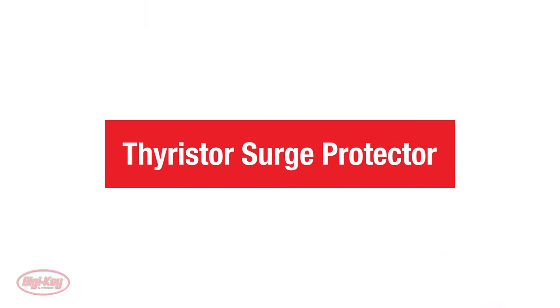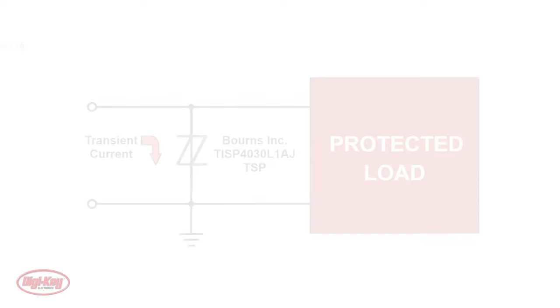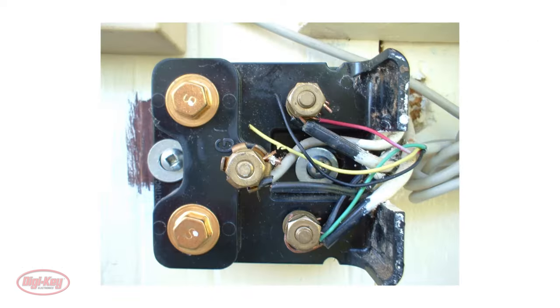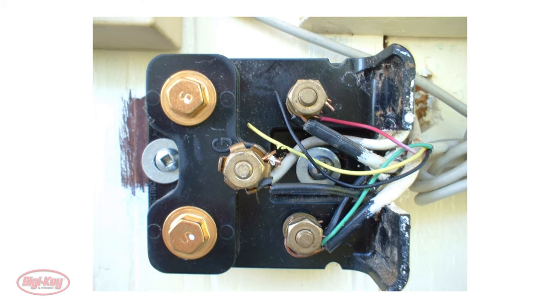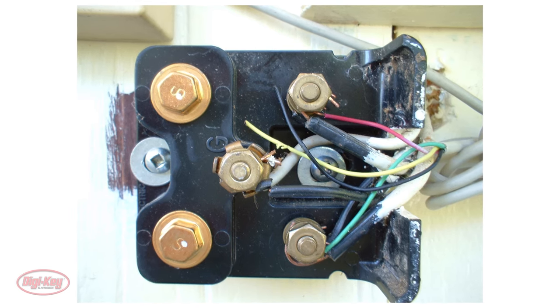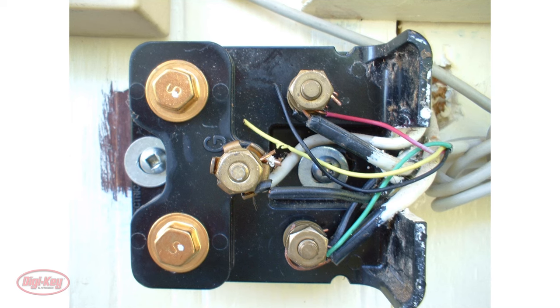A thyristor surge protector is a device that utilizes a thyristor to protect circuits from transient voltages. It is also connected in parallel with the load to be protected. But the thing that makes a thyristor surge protector different is that once it conducts, even if the transient has subsided, it will not restore to its non-conducting state unless the current through it is interrupted or drops below the minimum holding current. However, the high current capability of a thyristor surge protector makes it ideal for communication and control lines exposed to lightning. For example, the TISP4030L1AJ is designed to limit overvoltages on digital communication lines.